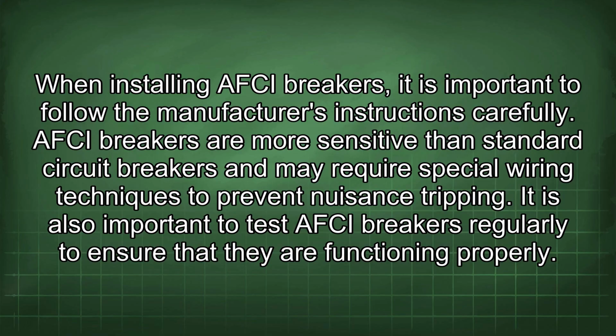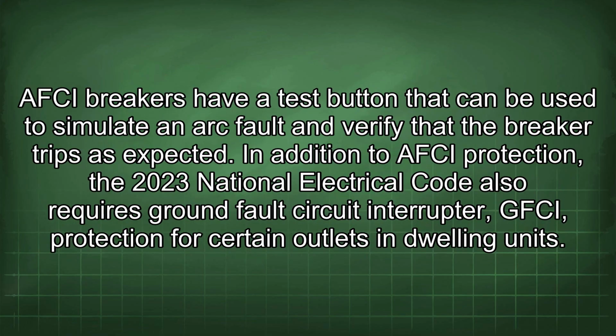When installing AFCI breakers, it is important to follow the manufacturer's instructions carefully. AFCI breakers are more sensitive than standard circuit breakers and may require special wiring techniques to prevent nuisance tripping. It is also important to test AFCI breakers regularly to ensure that they are functioning properly. AFCI breakers have a test button that can be used to simulate an arc fault and verify that the breaker trips as expected. In addition to AFCI protection, the 2023 National Electrical Code also requires ground fault circuit interrupter (GFCI)